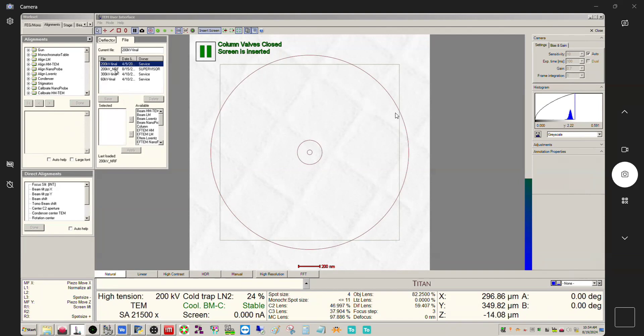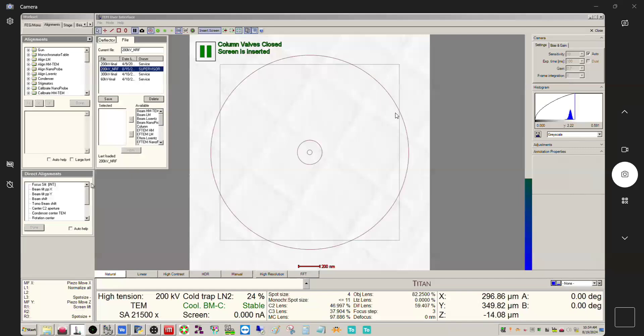The ones that are done at the service level you can't modify or delete or overwrite unless you're logged in as service. If you want to write your own alignment file you can do that at a supervisor level. If you're logged in at just a user level you can load alignment files but that's it. You can't actually save them, overwrite them, modify them, delete them.